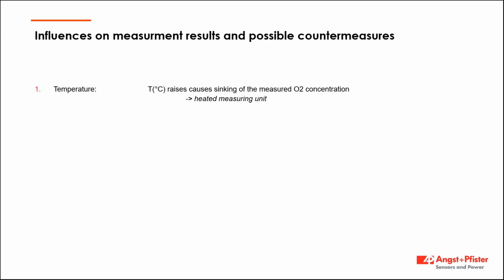And therefore, the measurement system itself has less oxygen in between this area where it is relevant, in that area where you have the dumbbell. The consequence is that the electronics thinks there is less oxygen, so the signal is lower, and therefore I give less current, meaning the output of the oxygen sensor is less, even though you have exactly the same amount of oxygen within the measuring cell.